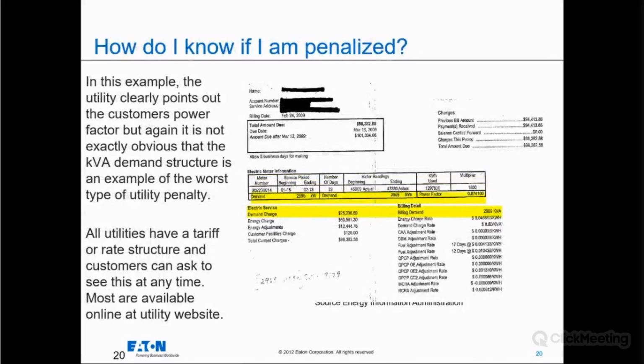Here we see another example. This is kVA. So again, if your demand charge is based in kVA, what did we already determine? kVA has a kW component and a kVAR component. So if you can reduce the kVAR component, you can eliminate and reduce the penalty by lowering the kVA to where it more closely matches the kW. Because if you had no reactive power usage, your kVA would match your kW. So here you can see in this bill, their kW was 2,595. Their kVA is 2,969, and their power factor is 0.874. So they could certainly reduce the demand charge that they're paying by increasing the power factor ratio closer to unity, or closer to 1.0, which would be eliminating the reactive power or drawing it down.